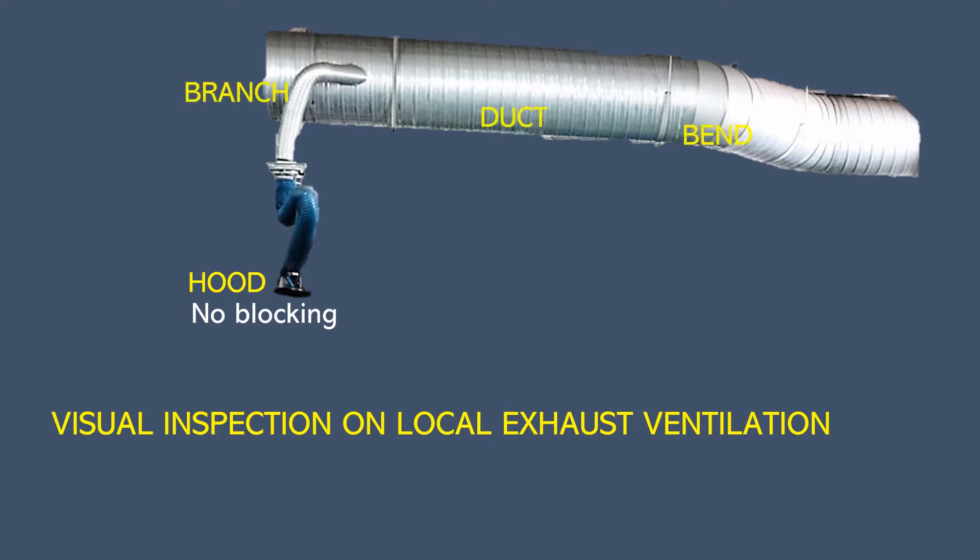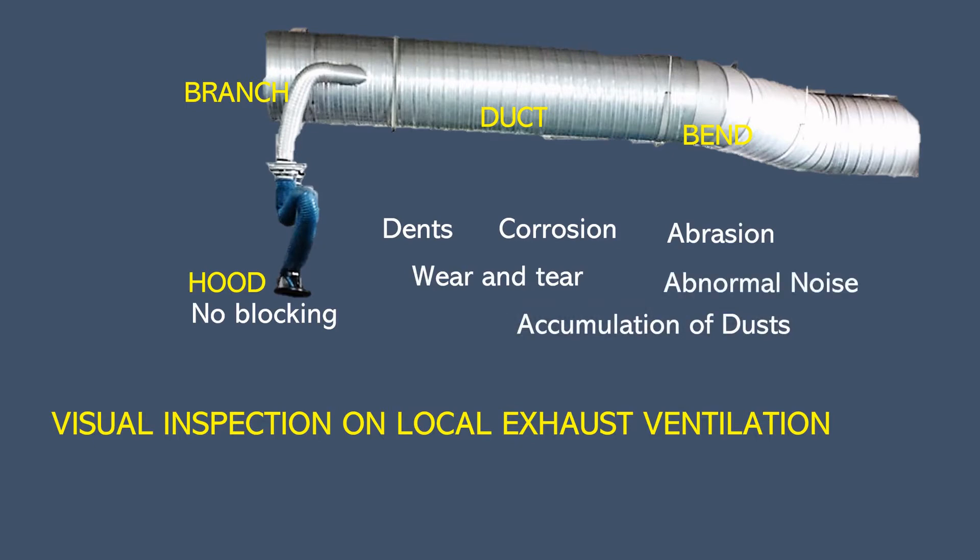Then at the branch, ducts, and at the bends, we need to check whether there are any dents, corrosion, abrasions, wear and tear, accumulation of dust that may interrupt the system, and also any abnormal noise that may indicate loose joints between the bends or maybe irregular operation of the fan. This inspection must be performed at least every 12 months for a welding workshop under normal usage. Any damage identified must be reported in written in the inspection report.